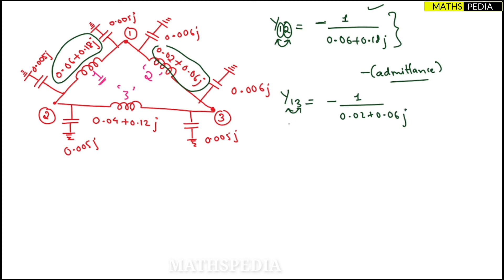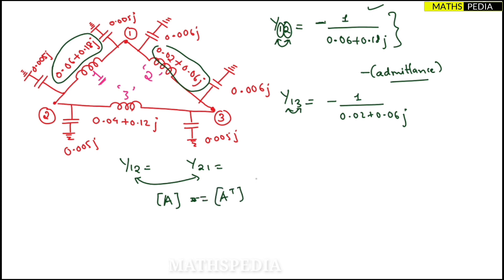Y13 = −1/(0.02 + j0.06), since that is the impedance between nodes one and three. Also note: Y-bus is a symmetric matrix, meaning Y12 = Y21 and Y13 = Y31. A symmetric matrix means A equals its own transpose.